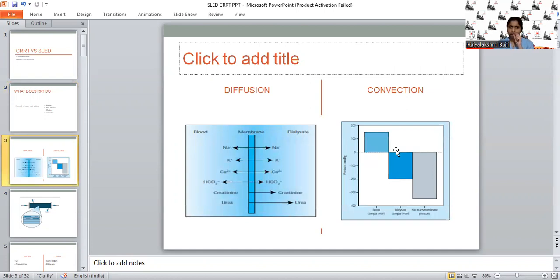How does diffusion happen? There will be transfer of molecules across the dialysis membrane, and this exchange happens along the concentration gradient. Blood circulates on one side of the membrane and dialysate fluid on the opposite side. By altering the concentration of various molecules in the dialysate fluid, we can alter the rate of diffusion, which also depends on membrane permeability and charge of particles.